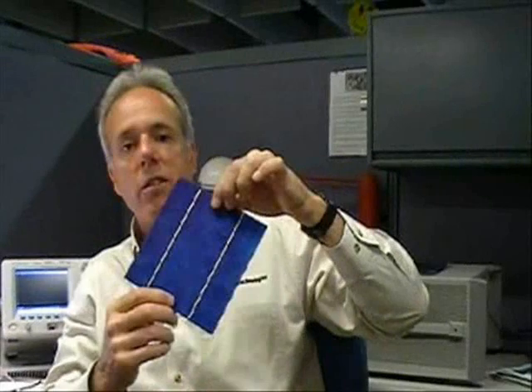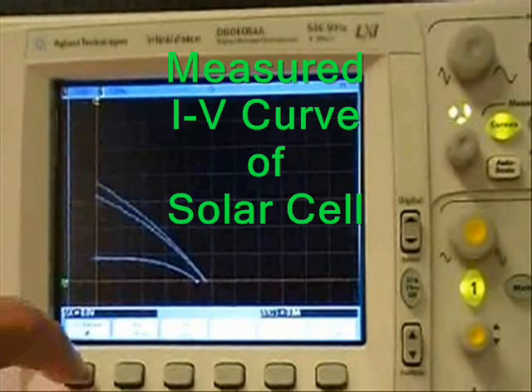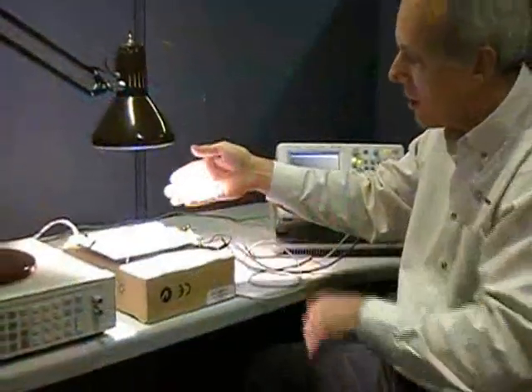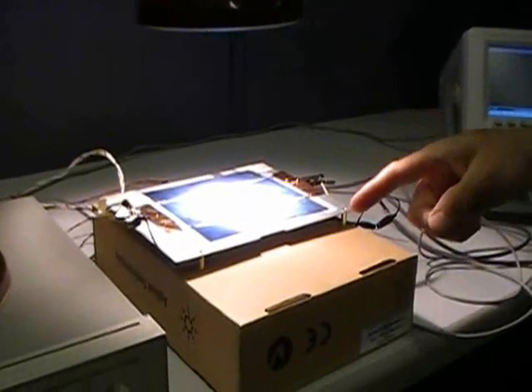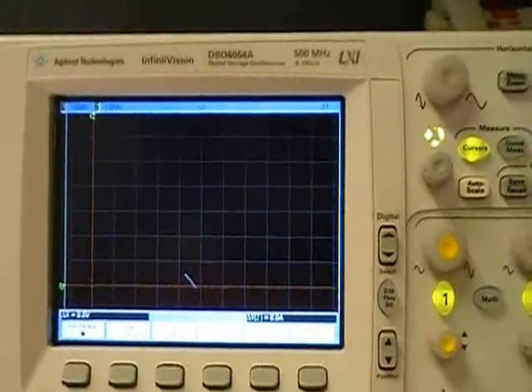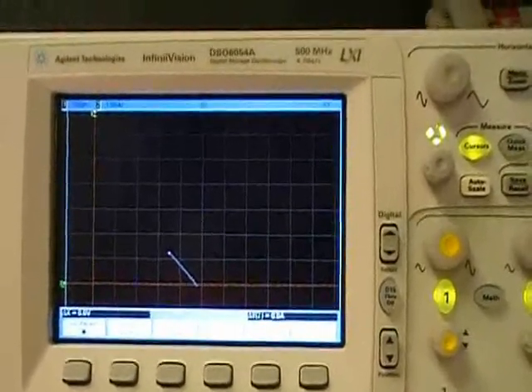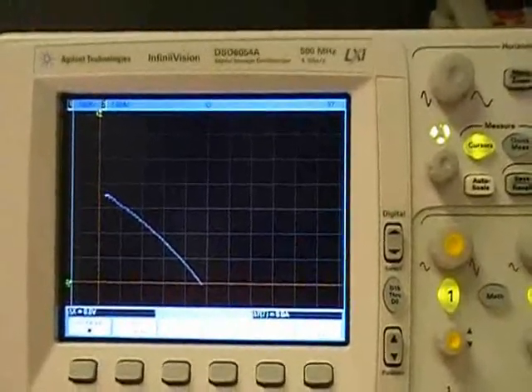I have here an individual solar cell. What I'll do next is measure the IV curve of this solar cell under various illumination levels to show you what a solar array simulator is expected to simulate. I'm using a floodlight to illuminate the cell and drawing current from the cell with a power supply acting as an electronic load. I'm also using an oscilloscope in XY mode to capture the solar cell's IV curve, with current on the vertical axis and voltage on the horizontal axis. I'm capturing this IV curve by slowly turning up the current drawn from the cell under full floodlight illumination.